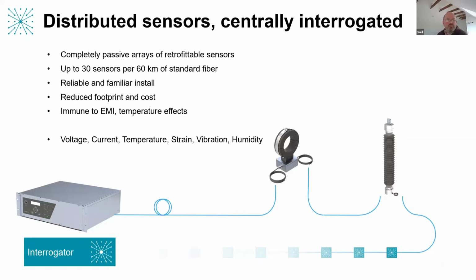This was designed to do protection and metering in high voltage systems, protection and control functions. But because it's so accurate and good enough for that, while there isn't a fault, it's collecting a lot of data from a lot of locations, which are giving you the early warnings and predictors of an impending failure. And in particular, looking at harmonics and power quality and power factors here. So that's the concept of the technology, and we wanted to explain that it's scalable, it reaches a lot of locations.